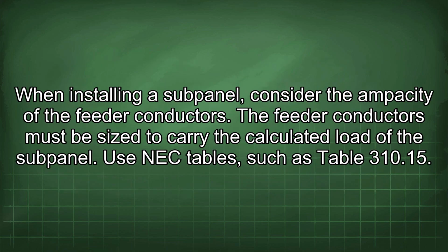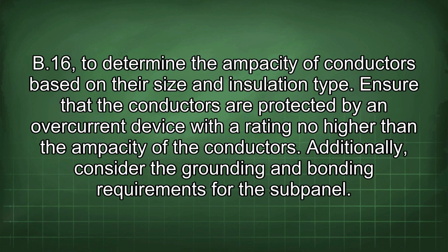When installing a subpanel, consider the ampacity of the feeder conductors. The feeder conductors must be sized to carry the calculated load of the subpanel. Use NEC tables, such as Table 310.15(B)(16), to determine the ampacity of conductors based on their size and insulation type. Ensure that the conductors are protected by an overcurrent device with a rating no higher than the ampacity of the conductors. Additionally, consider the grounding and bonding requirements for the subpanel.